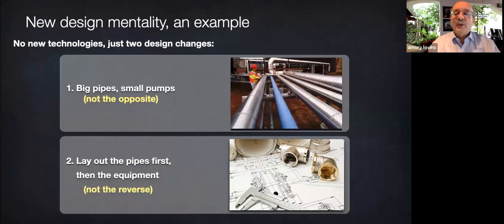We lay out the pipes first, then the equipment they connect, not the reverse. The logic is simple. Friction inside the equipment doesn't depend on where the equipment is, but friction in pipes between the equipment matters. It depends a lot on where it is. So the geometry that optimizes different devices' locations can minimize friction. Traditionally, we put the tanks, boilers, and so on in some convenient, arbitrary, traditional place, and then we call in the pipe fitter and say, please come connect point A to point B. But by then, A and B are rather far apart. Other stuff got in the way between them. They're at the wrong height. They face the wrong way. By the time the pipe snakes across the space, all dressed in neat right angles like they teach us in trade school, it has about 3 to 6 times the friction that it would have had with a straight shot.